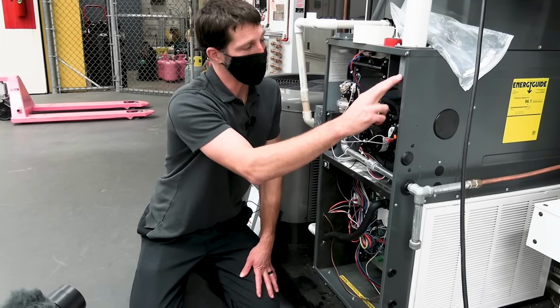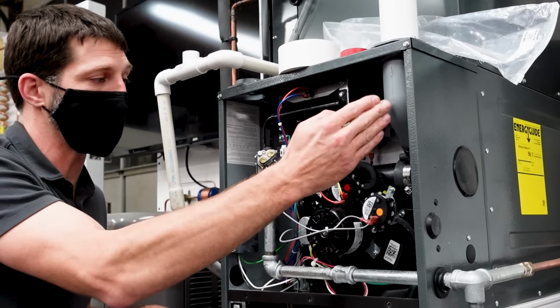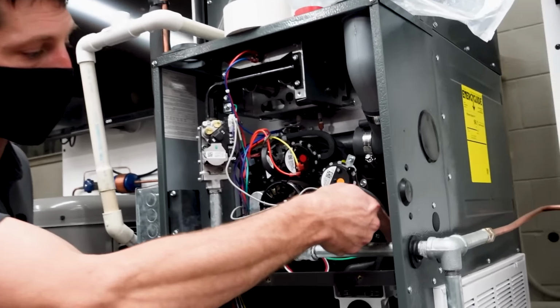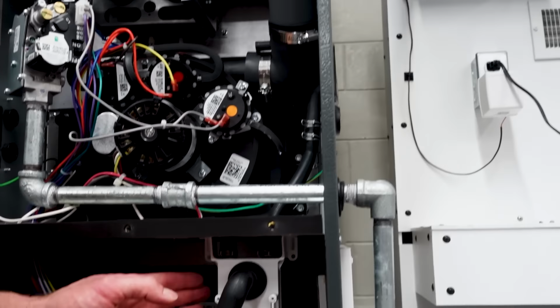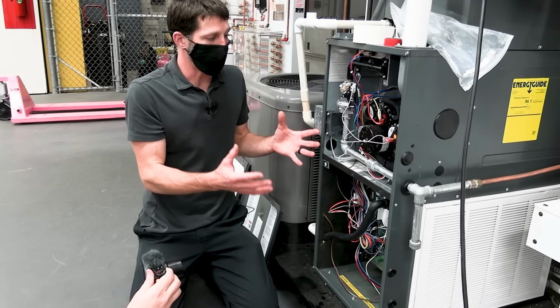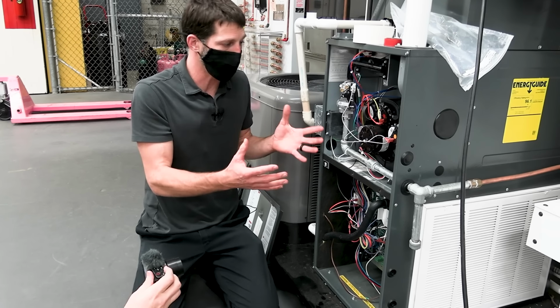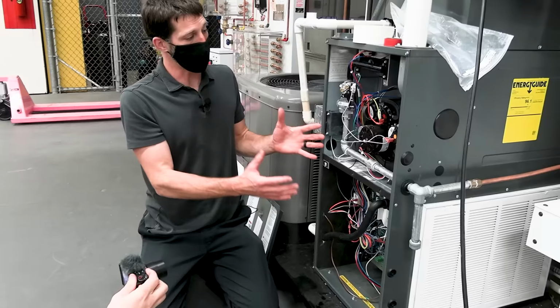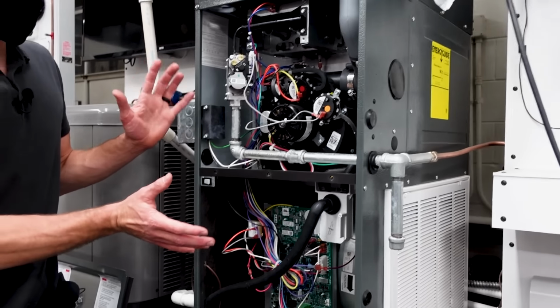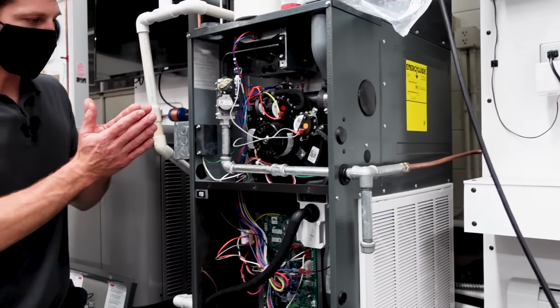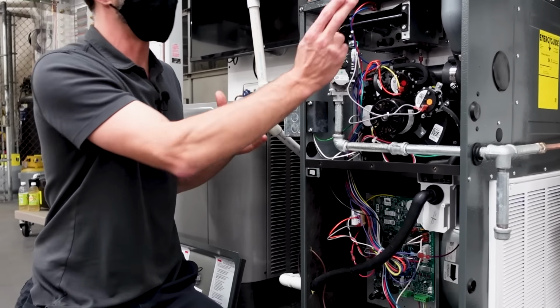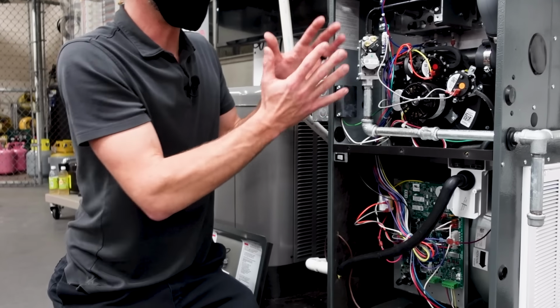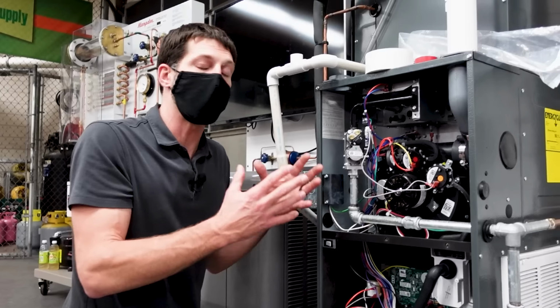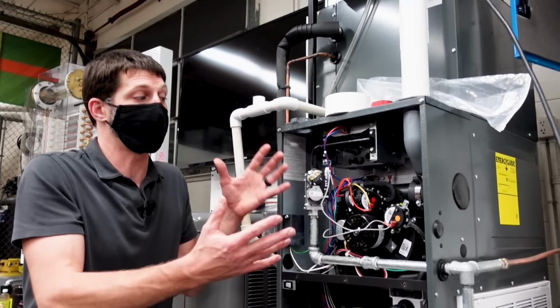And so if you have any condensation in a 90% efficient furnace, you have this tube where it's going to catch and go into your trap that's down here. Condensate, so water vapor, is a byproduct of the combustion process, and so you're always going to have that. And this, I believe, is a 96% efficient furnace, but anything that's an 80% efficient furnace has a metal exhaust pipe, but anytime you have a 90% efficient furnace, it's gaining its extra 10% of efficiency, in this case 16% efficiency.